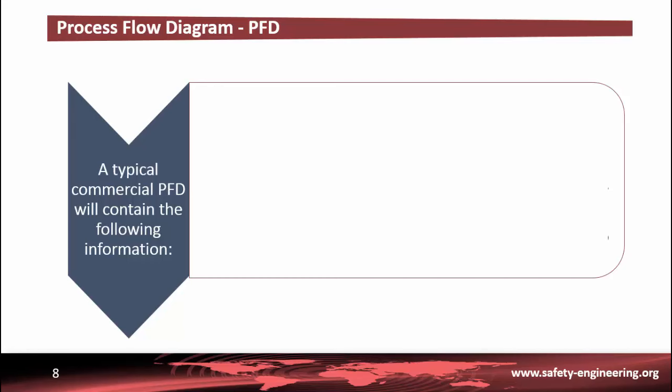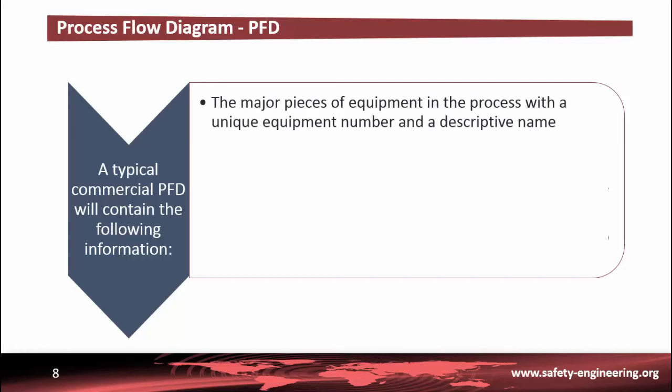A typical commercial PFD will contain the following information. First, all the major pieces of equipment in the process are represented on the diagrams along with a description of the equipment. Each piece of equipment is assigned a unique equipment number and a descriptive name. Second, all process flow streams are shown and identified by a number. A description of process conditions and the chemical composition of each stream is included. These data are either displayed directly on the PFD or included in the accompanying flow summary table.